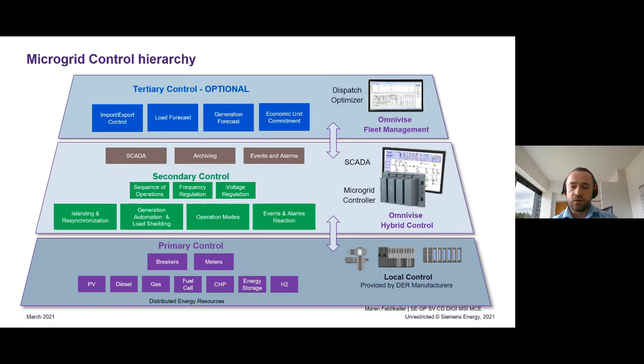On top of that, at a secondary level, comes the microgrid controller, which makes sure all the generation and load assets work in a coordinated way. This level of operation is provided automatically, working on a sub-second level, practically 100 to 500 milliseconds, providing secondary control of frequency, voltage, event management, and so on.